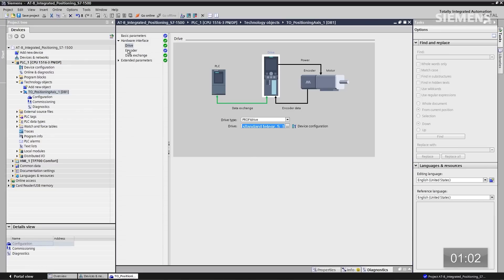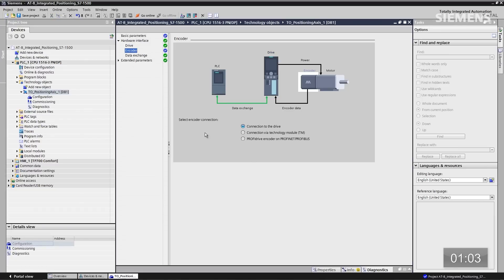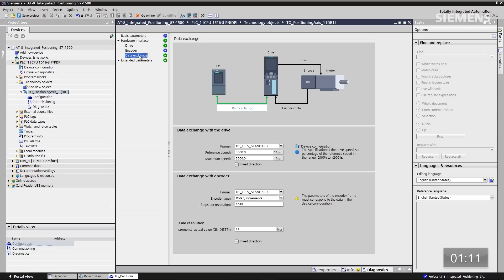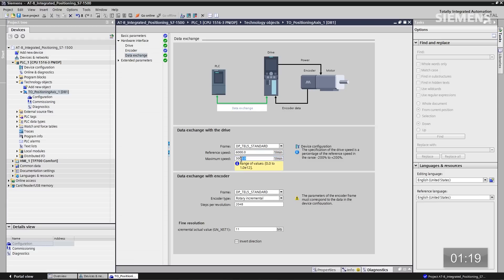Let's go to the encoder now, and you can see we already have a defined connection to the drive — that's the default, so we can accept that. Let's go to the data exchange, and I need to change a couple of things. The reference speed needs to be 6,000 — click enter. And the maximum speed the same thing: 6,000.